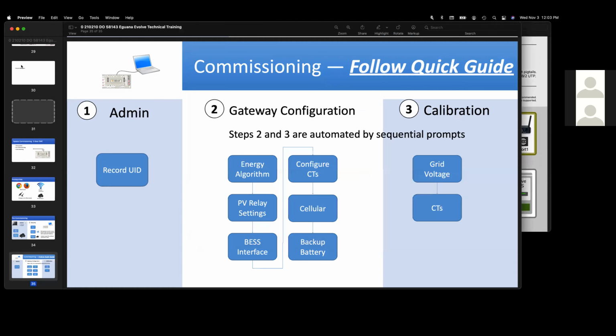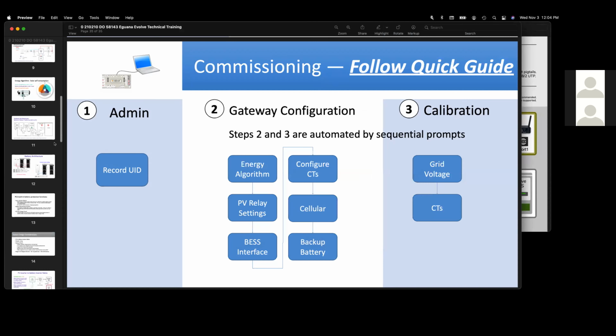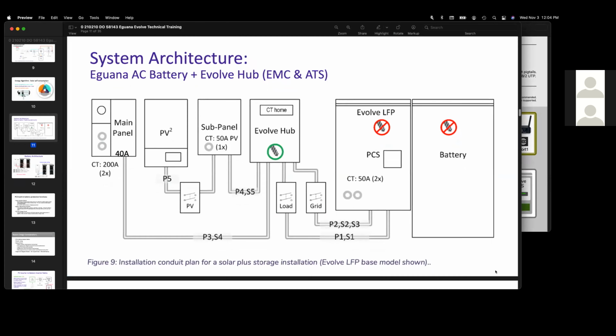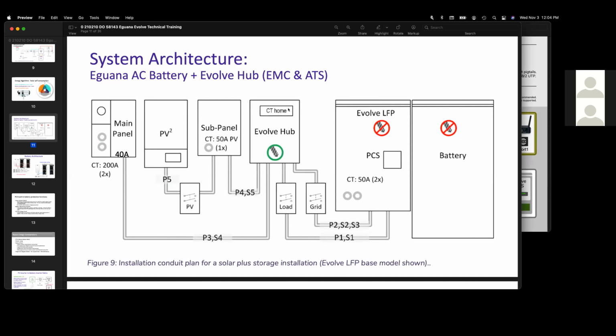Let me pull that up here. On this slide, Tafara, the Evolve Hub is the smaller enclosure in the middle. That is the gateway that provides monitoring via CTs and communications interface with the battery. It measures PV generation, it measures home loads, and it communicates with the battery to tell it to charge and discharge. The battery inverter is located within the PCS cabinet of the Evolve LFP in this case, and the hub itself just provides monitoring and control and communications.